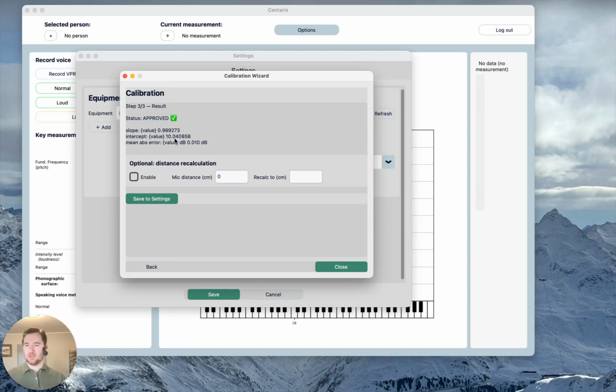Now, of course, when you're really going to calibrate in your own profession, you're going to see slightly different changes, and the slope might be a little bit more or a little bit less than 1, and the intercept might even go up to 40 decibels or 6 or whatever. So what these numbers are telling you isn't really how reliable the difference was, but what is going to tell you this is the mean absolute error, which is 0.01 decibel, so that's really low. You want this to be lower than 1 decibel. So when your mean absolute error is below 1 decibel, you've calibrated correctly. So that's why status is approved.